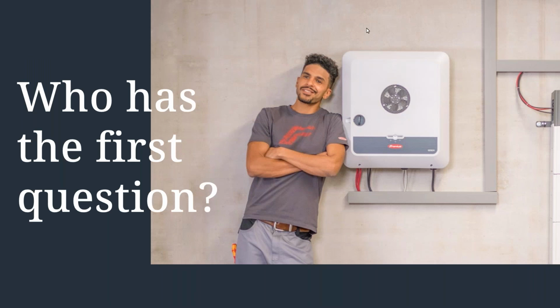Someone asked, with a 5 kilowatt inverter, what is the highest stack you can have? If it was a 5 kilowatt Symo Gen24 Plus, the 3-phase inverter, then you could have the 15.8 kilowatt hour stack - that's the largest. However, with single phase, say the Primo Gen24 Plus 5 kilowatt inverter, you can only have up to 9.5 kilowatt hours. So it depends if we're talking single phase or 3-phase.